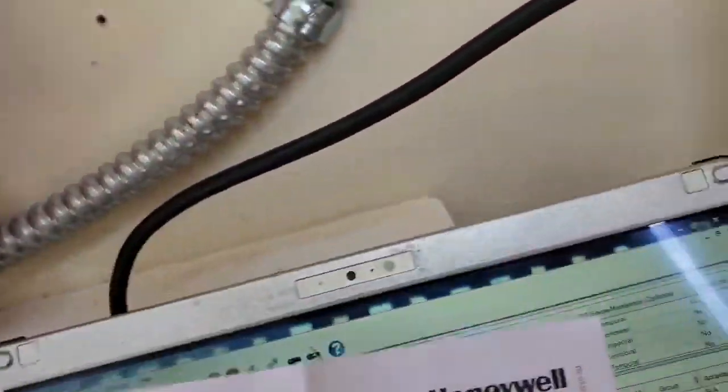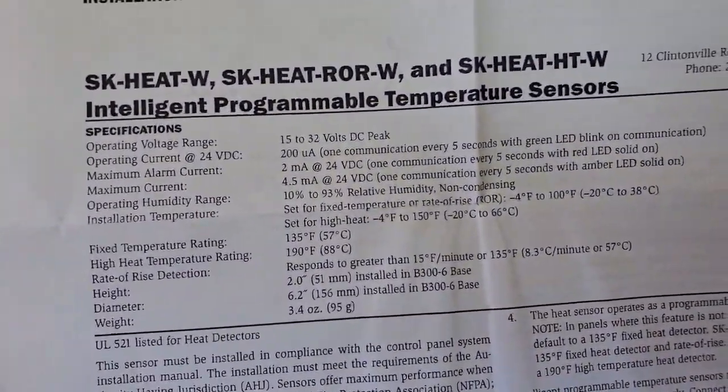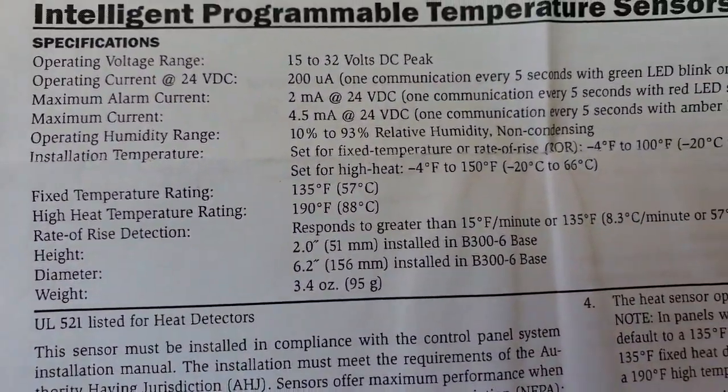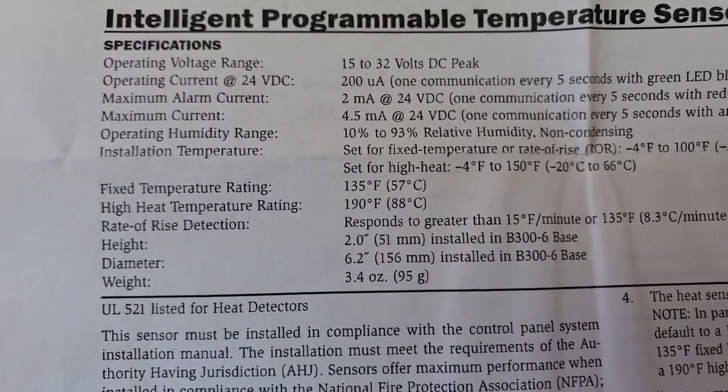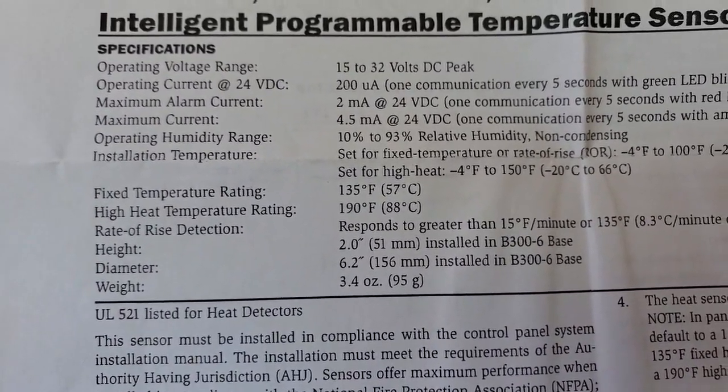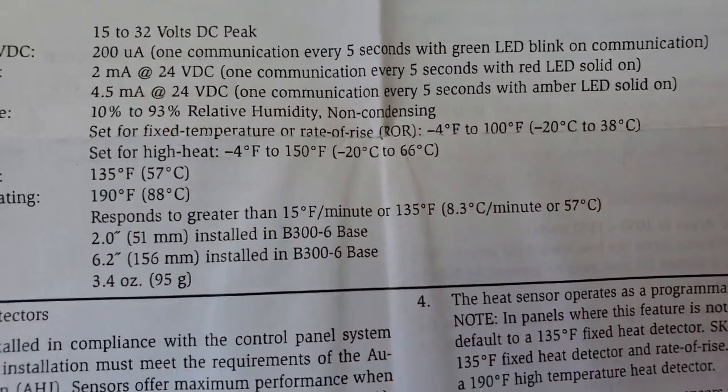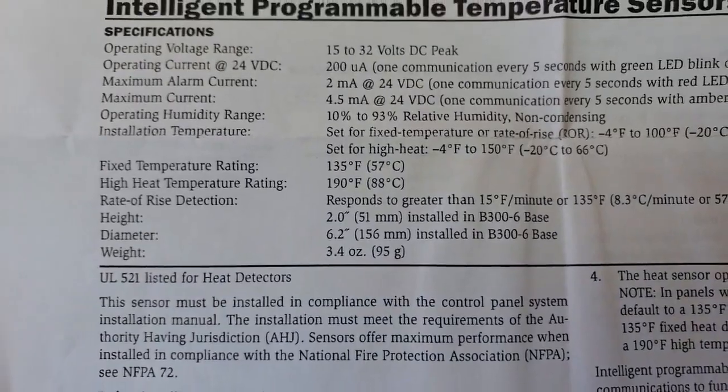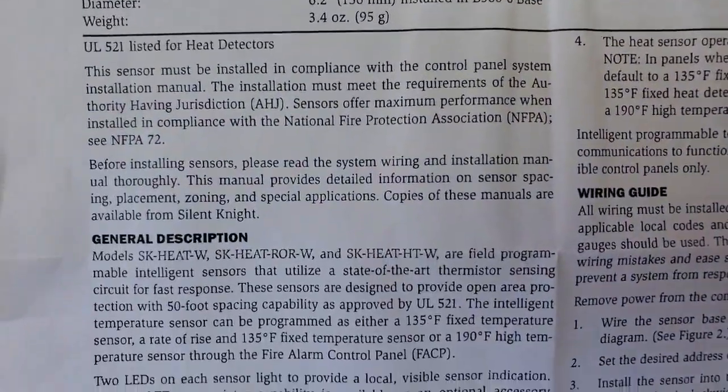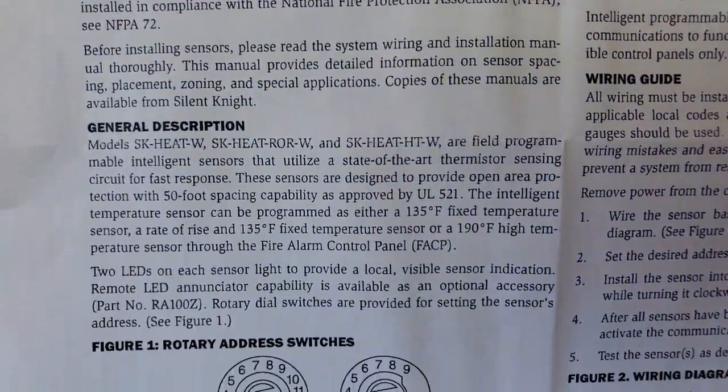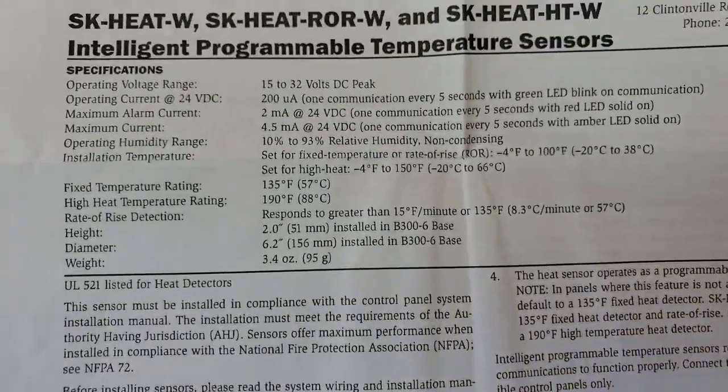So as I'm looking at this now, here's the instructions for the heat detectors. Fixed temperature rating, 135. High temperature rating, 190. Rate of rise. This doesn't say anything about a variable temperature setting.